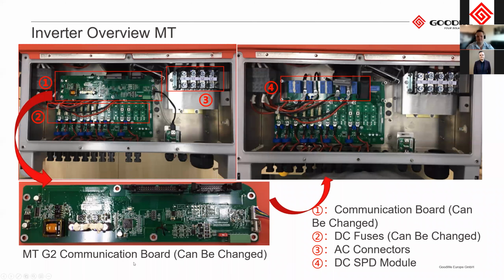And this is the control board, but this is a much older control board than what we have in our devices now. It looks quite a lot different. Over here on the new control boards, we have our remote disconnect. So I'll just pan through to our user manual for you as well for this. And then we have our RS485 connections here. So this one is pointing downwards, but our RS485 connections are pointing upwards now.